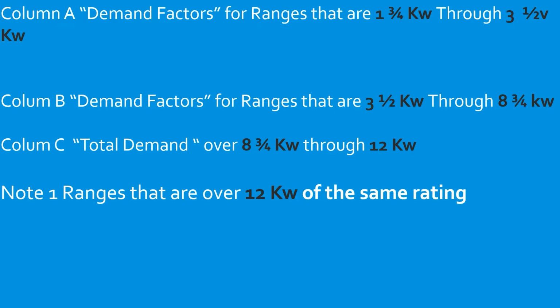So we have to be mindful of our notes when we're dealing with this, because column C only goes up to 12 kW, doesn't it? So let's go down to note 1. It's right underneath your table. It says over 12 kW through 27 kW of all the same rating. For ranges rated more than 12 but not more than 27 kW, the maximum demand of column C shall be increased by 5% for each additional kW rating or major fraction thereof by which the original individual value exceeds 12.